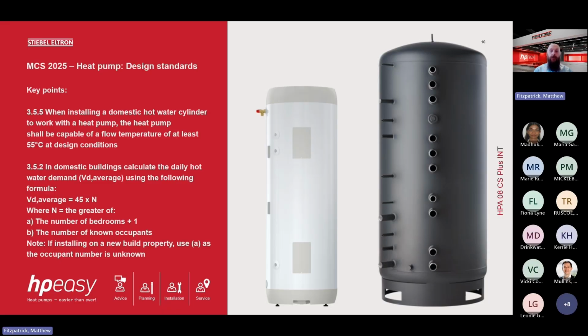It's also crucial to make sure that the coil size is correct for the heat pump output as well. And with a cylinder of 180 litres, you need to ensure it's a heat pump cylinder, because if the coil size is too small, again referring to the previous slide, the heat pump cannot deliver the energy required and it will go out into a fault state.